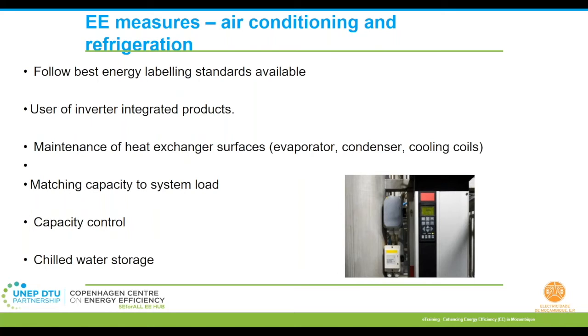The first and foremost, we need to try to have the best energy labeling standards available. Lately, we are getting some inverter grade integrated products also for air conditioning units. The normal split ACs do come with inverter options also, which actually consume much less power compared to the conventional ones. Then for larger systems, generally the heat exchange happens over the heat exchanging surfaces, so they have to be maintained. That is the evaporator, condenser coils, and cooling coils and all.